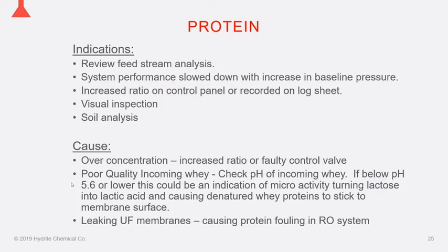Again, this is also going to be identified most easily from a visual inspection. So this is going to be your autopsy, pulling a membrane out and actually looking at what's on the surface. But the ultimate resolution is going to be, again, targeting that specific soil.